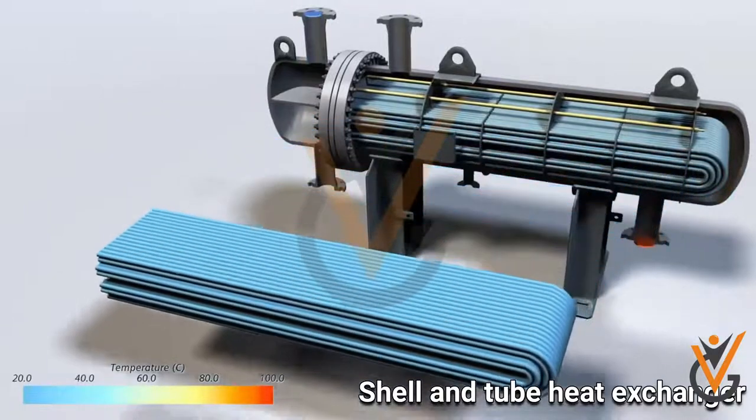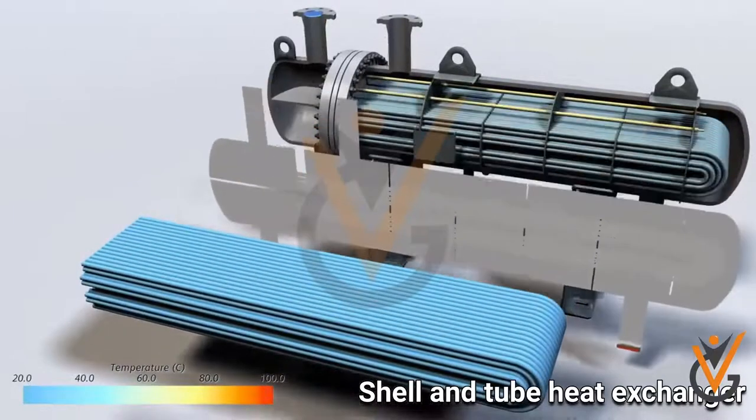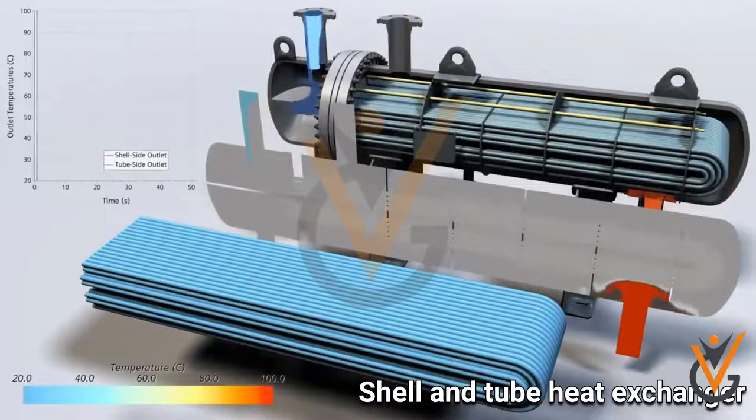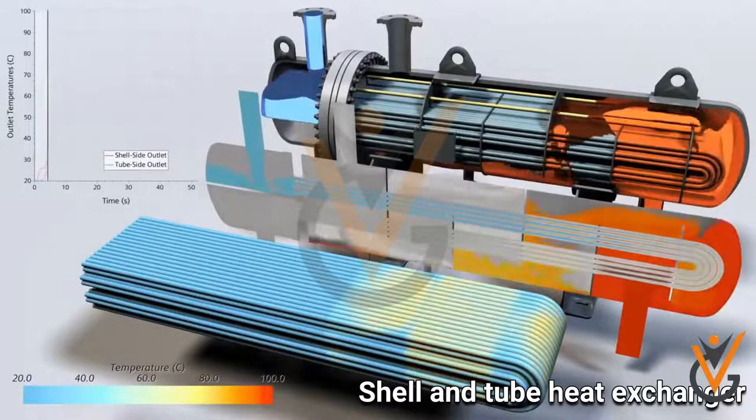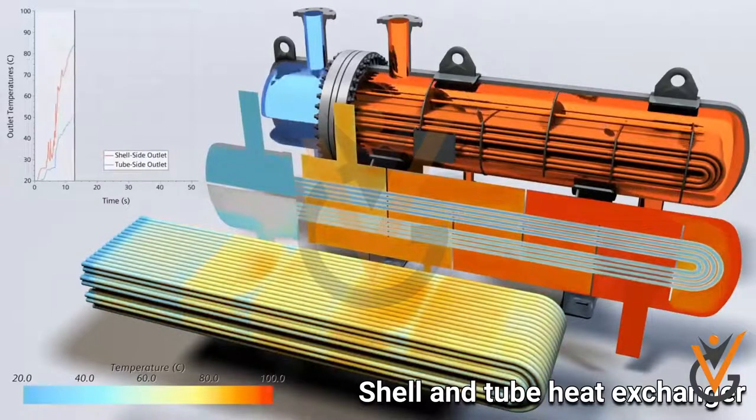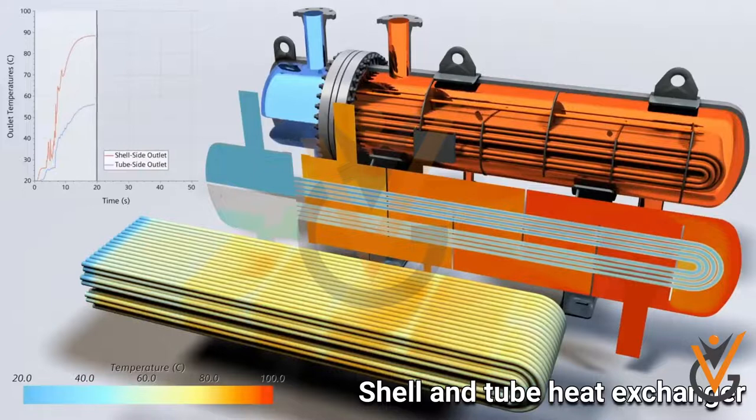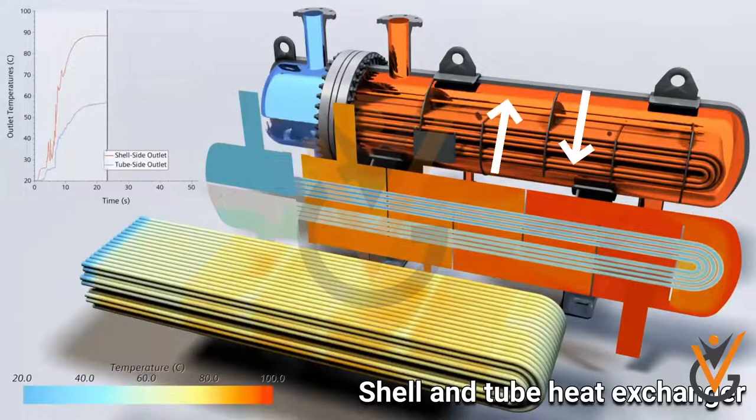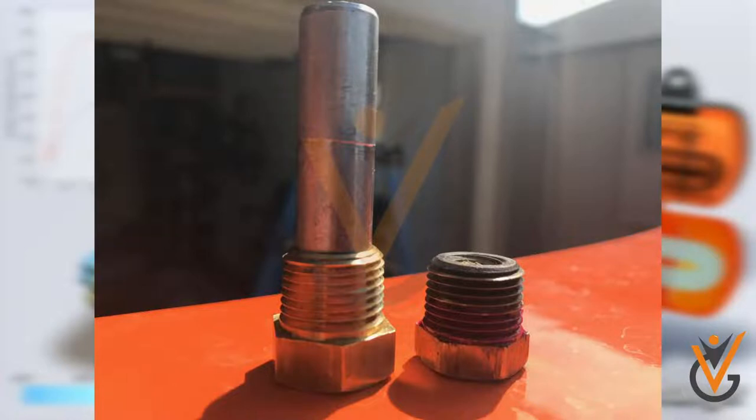One tube plate is fixed while the other is free to allow for expansion and contraction of the tube stack. Tubes pass through the baffles, which have a number of holes, providing intermediate support to the tubes. Baffles also create a mixed flow pattern for the fluid.